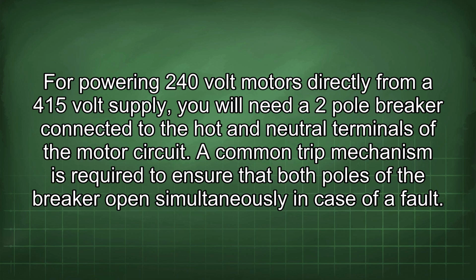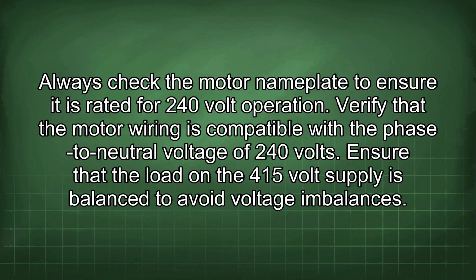For powering 240-volt motors directly from a 415-volt supply, you will need a two-pole breaker connected to the hot and neutral terminals of the motor circuit. A common trip mechanism is required to ensure that both poles of the breaker open simultaneously in case of a fault. Always check the motor nameplate to ensure it is rated for 240-volt operation. Verify that the motor wiring is compatible with the phase-to-neutral voltage of 240 volts. Ensure that the load on the 415-volt supply is balanced to avoid voltage imbalances.